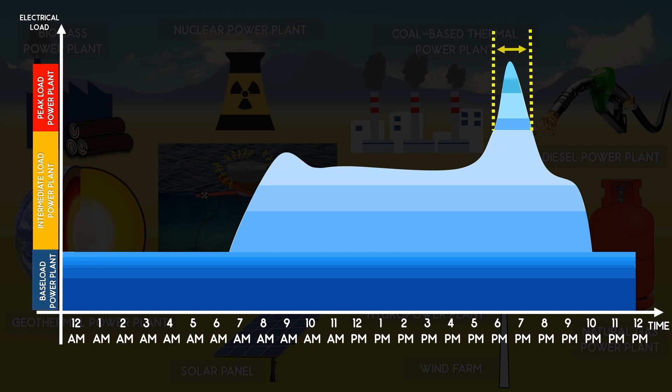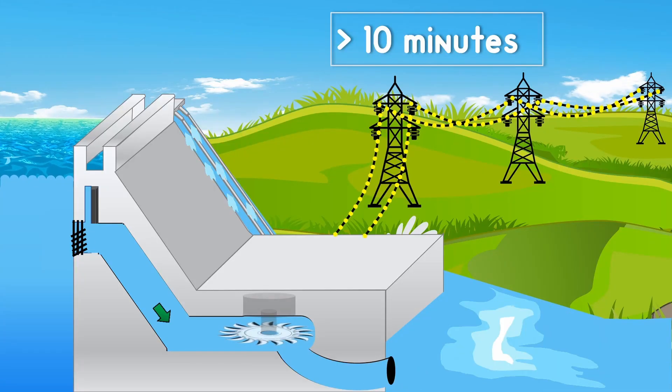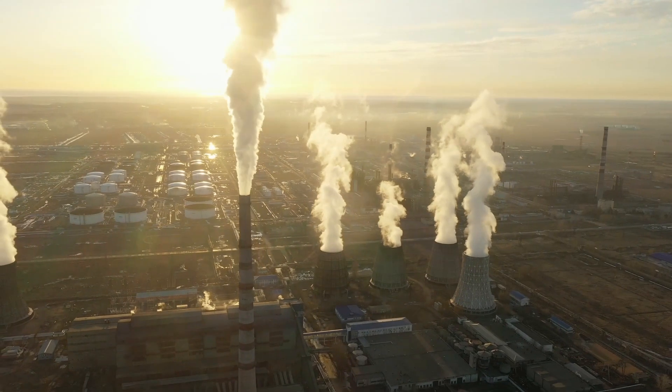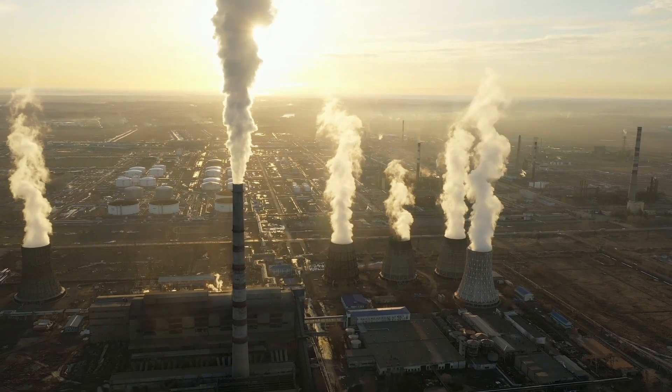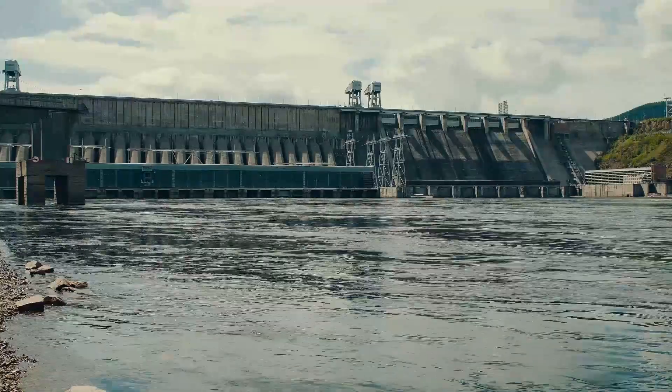Peaking demands are often for only short durations. So one of the qualities expected from the peak load power plants is that they should have a quick start-up time. The best thing about hydropower plants is that it can be started and brought to full power in less than 10 minutes. While thermal power plants requires hours to get started.